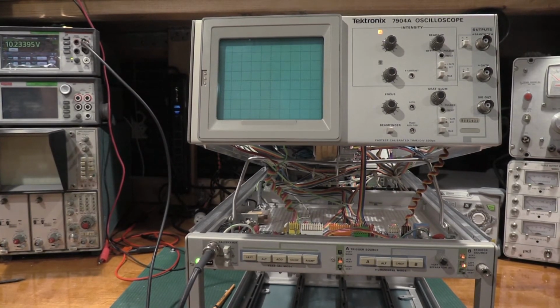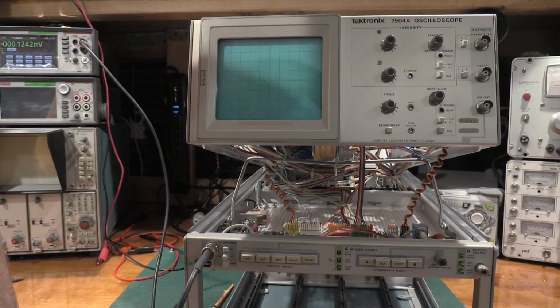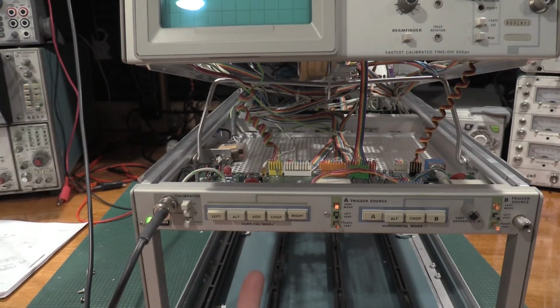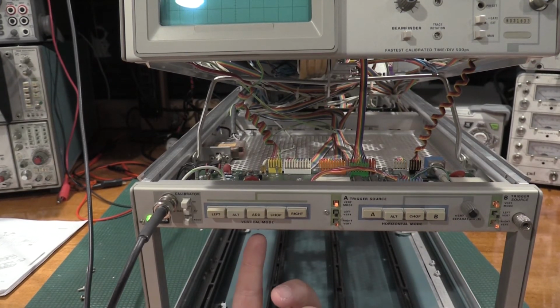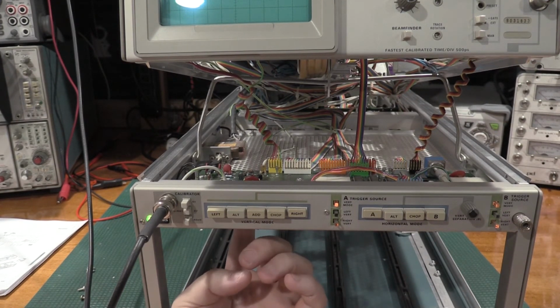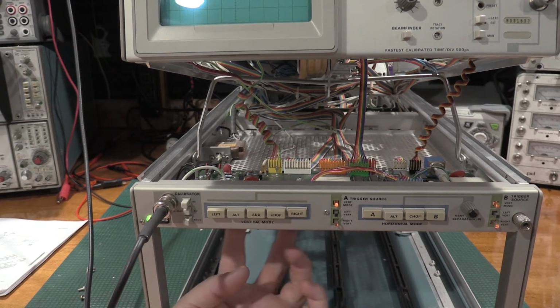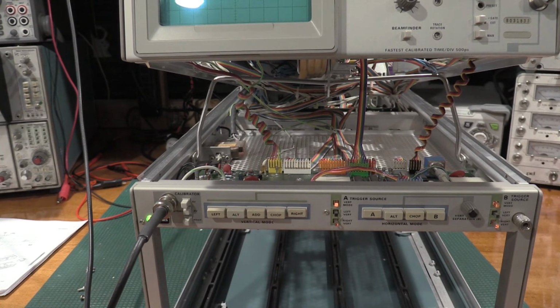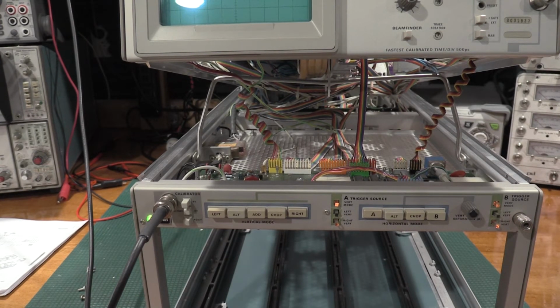Okay, gonna have to work on the calibrator. Don't I have to pull a transistor for this? Okay, to make it easy, you don't have to get under here. You have to get under here. The adjustment points for the 0.4 volts and the 1 kilohertz are on the bottom of the plug-in bay, and that's where you can get to them. The Rigol says I'm at 0.4 exactly, and the frequency counter says I'm at 1.008 kilohertz, so we're off by 8 hertz. If I turn it any more, the pot's going to fall to like 950, so I'm going to have to leave it there.